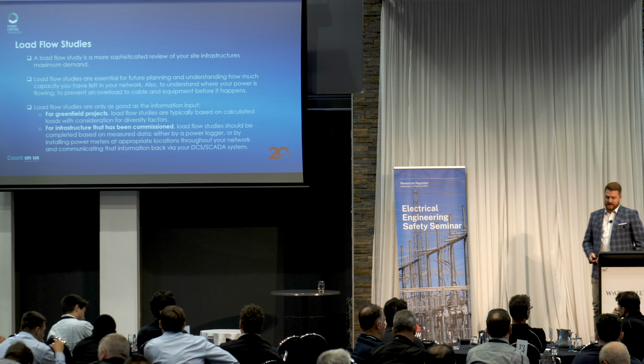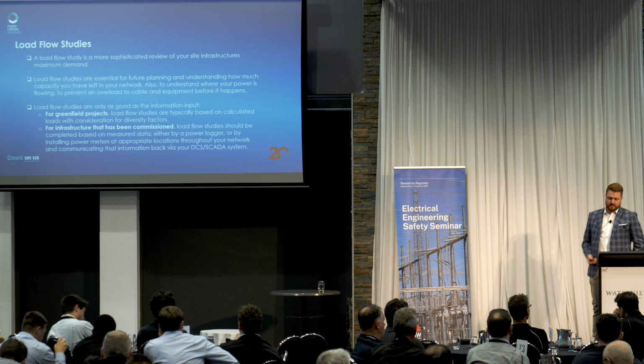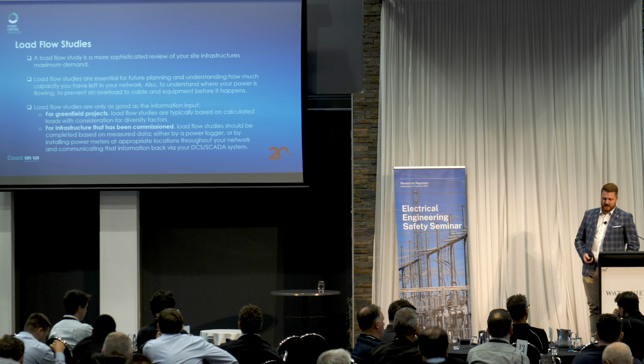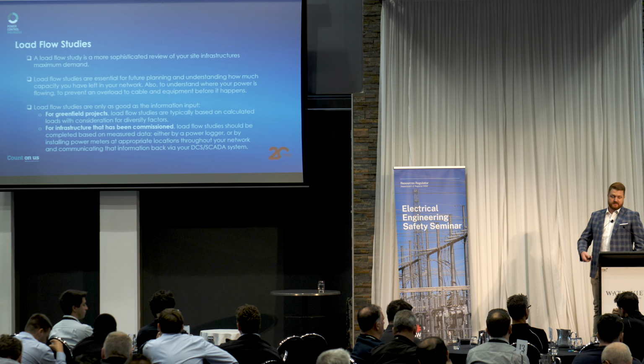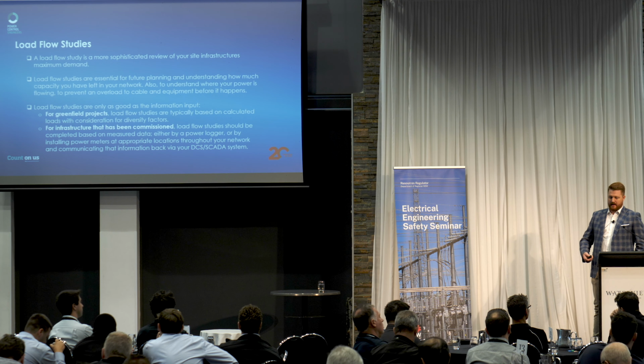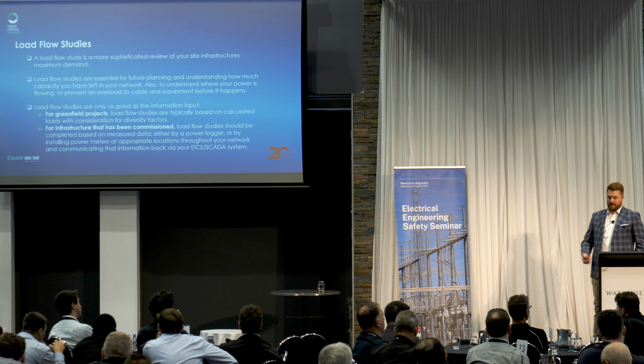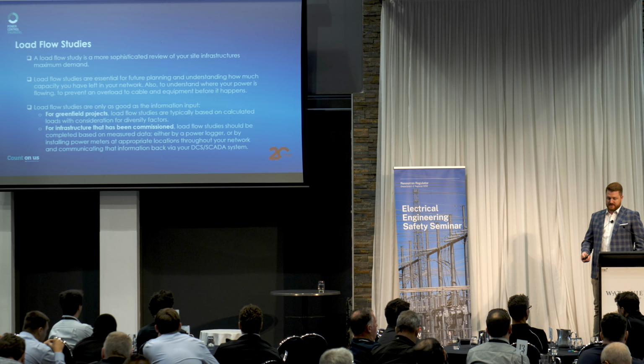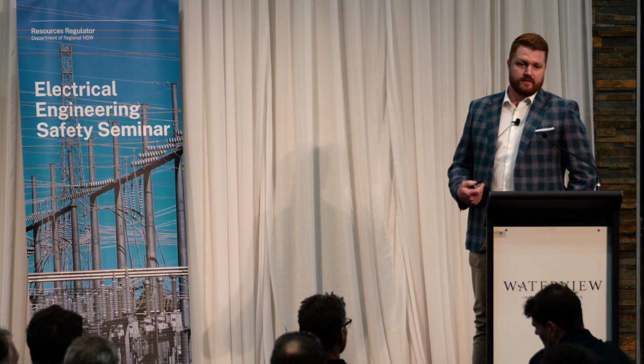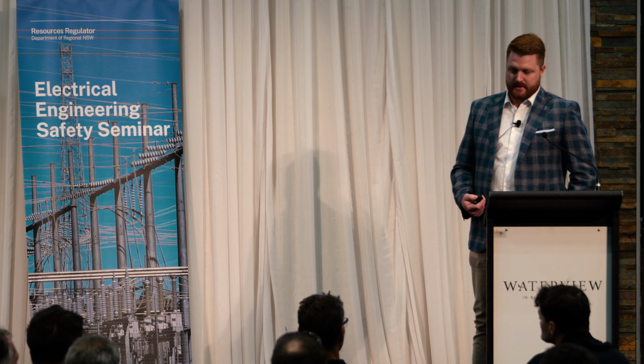Load flow studies are only as good as the information you put in, as per everything in power system modelling. So for greenfield projects and something that hasn't been built yet, your load flow will have to be relied on, typically based on calculated loads with consideration for diversity factors, whereas if it's been built and it's been commissioned, load flow studies should be based on measured data. There's nothing better than actual measured data, not calculated.